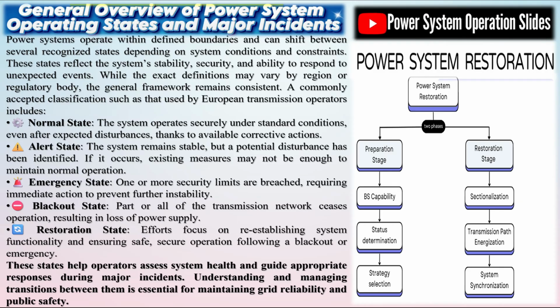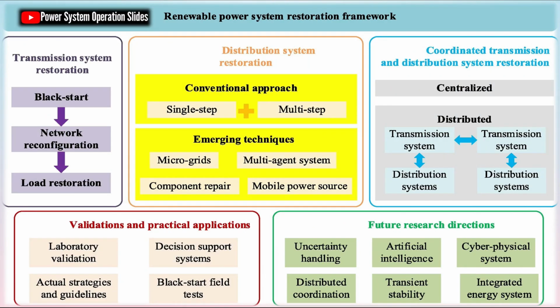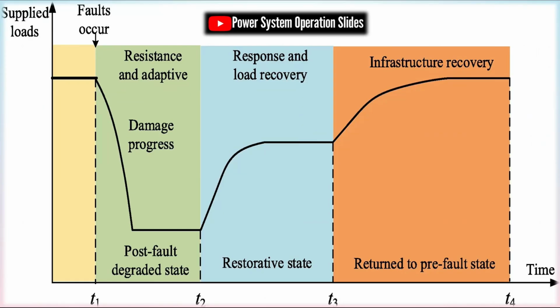Across international practices, two primary strategies are commonly used to restore power systems after major outages: the bottom-up and top-down approaches. Bottom-up strategy: this method relies on black start generators, units capable of starting without external power supply. It is typically used when the entire system is down and no support from neighboring grids is available. Restoration begins by energizing selected ultra-high voltage (UHV) transmission lines and forming isolated electrical islands. These islands are then gradually synchronized and expanded to restore load and system stability. Top-down strategy: this approach leverages support from interconnected neighboring systems. Operators first energize the main transmission backbone using external sources, then progressively restore local loads, restart generation units, balance supply and demand, and reconnect remaining areas.